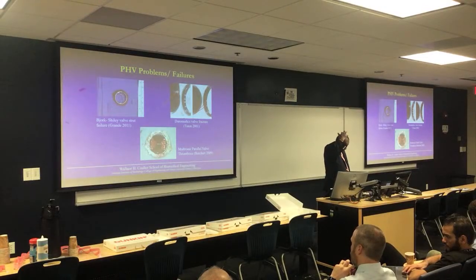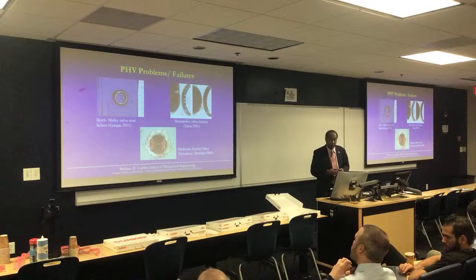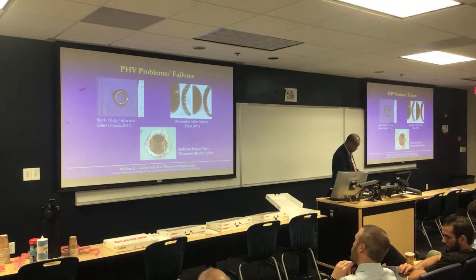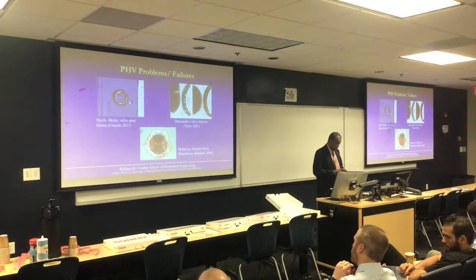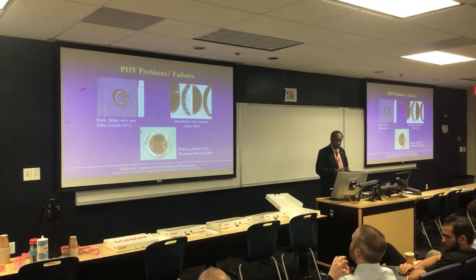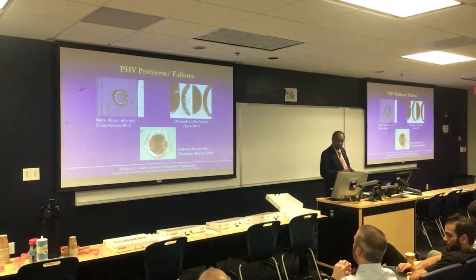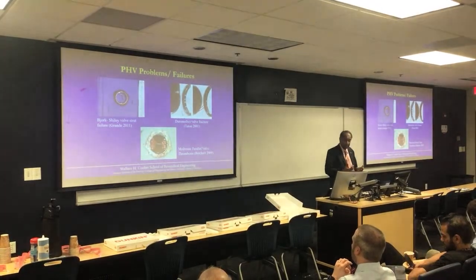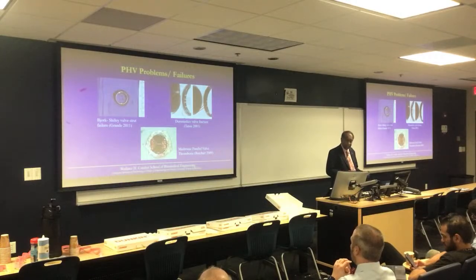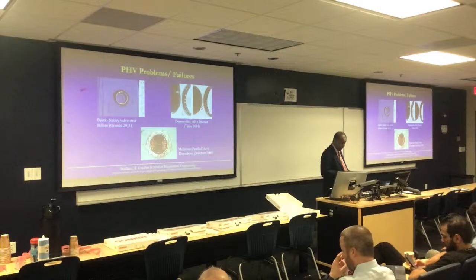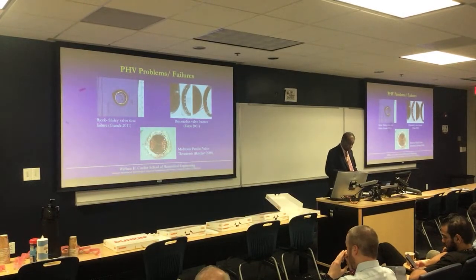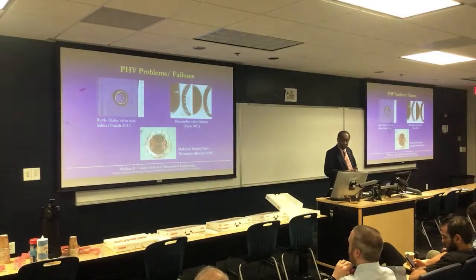This shows some of the issues that we face with mechanical valves. In the earlier ones, we did have valves that were mechanically not designed properly, or had manufacturing defects that led to failure. And this shows a Björk-Shiley valve where the strut broke. In the case of a mechanical valve, if there is mechanical failure, unfortunately, it tends to be in most cases catastrophic. Unless the patient gets to an emergency room pretty much immediately, the chances of survival are minimal.